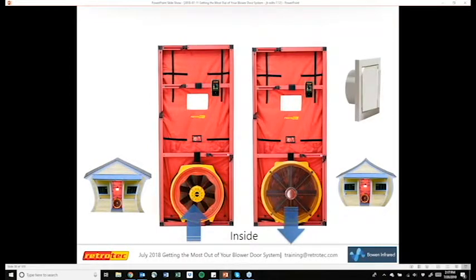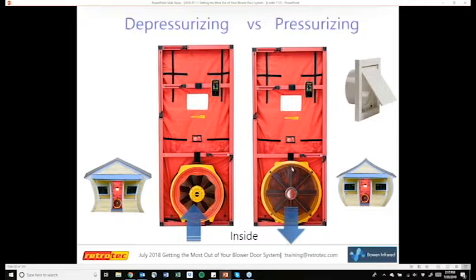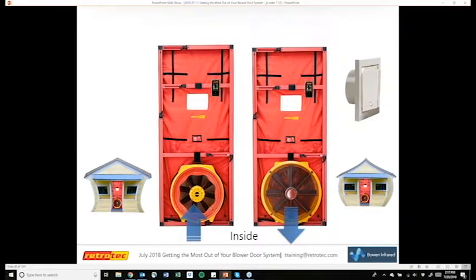And so this is looking at the difference between depressurization and pressurization. For most standards, both are acceptable. But one thing we recommend, if you have the choice, is depressurization, because on the envelope of your house, you have different dampers that go to various things, such as your bath fans, your kitchen exhaust, and dryers. If you do pressurization, like this damper here, it can blow those out and give you a higher leakage number. And for most standards, you're not allowed to go around and tape these kinds of things off. So if you do depressurization, it'll pull them shut to give you a tighter number.